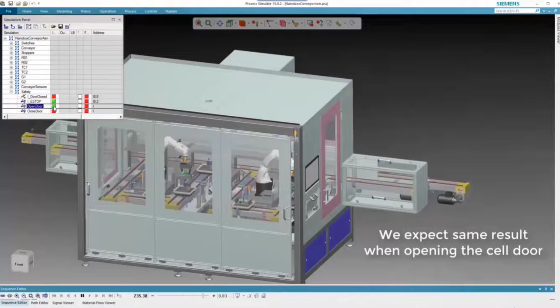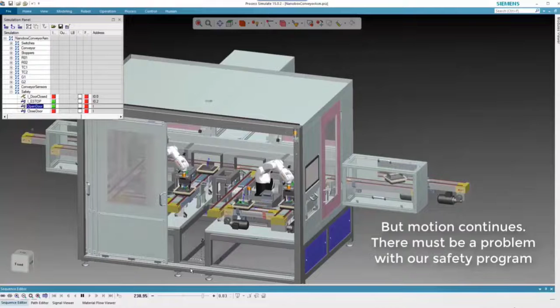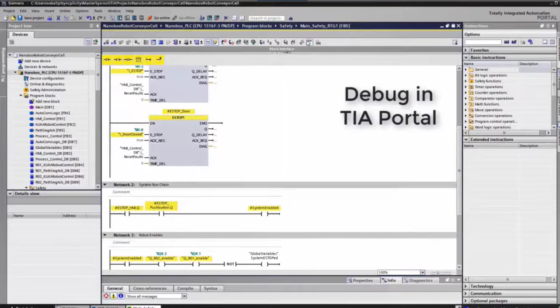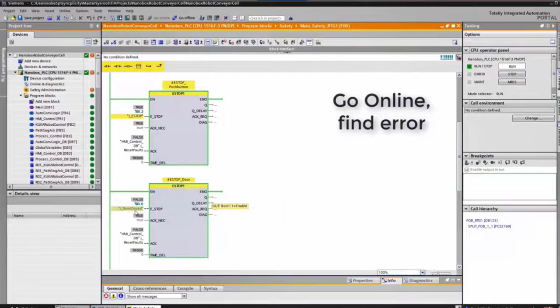A typical use case is testing for safety. In this case, we want to test for fail-safe and emergency situations. We can see that when triggering the door opening by the operator, safety isn't triggered and production of the machine doesn't stop as planned. This is a critical error we must look at. We'll take a look at the PLC code while staying online with the simulation, which helps us emulate what we can really do even in production.